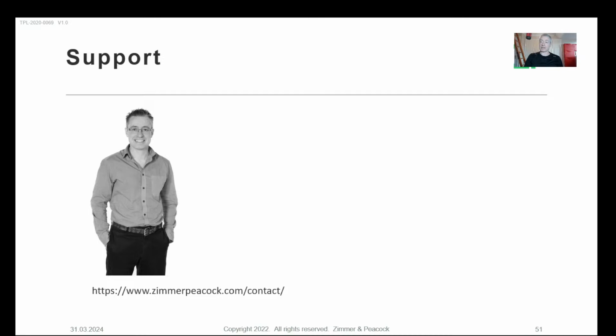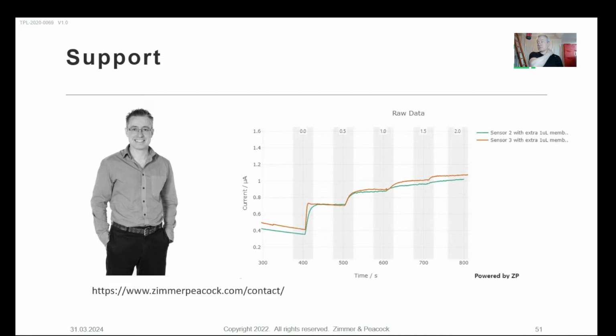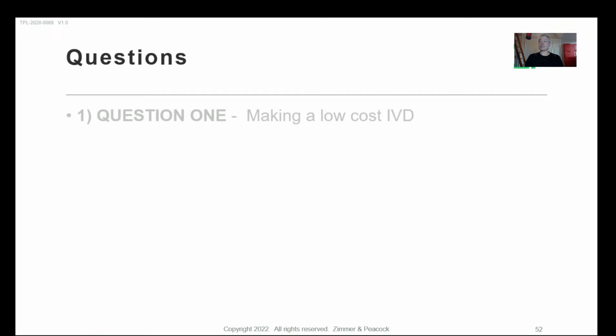Well, they are a paying customer, so therefore we'll get online with them and give them support because we know what we're expecting, but they're not getting it. But the nice thing about doing these webinars is when you think about, well, they're using these electronics and it works well on the potassium sensor, which is an ion selective electrode, which is an open circuit potential measurement, which actually uses the reference and working, and then they try to do a different type of assay, which is amperometric, where the counter is included. And I had an intuition that there's something wrong not with the sensor, but the electronics, and we'll take a look at that with them.